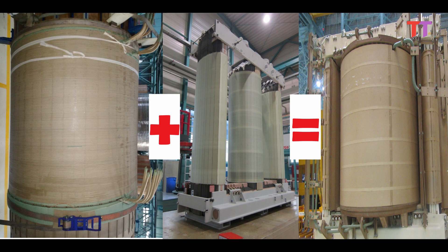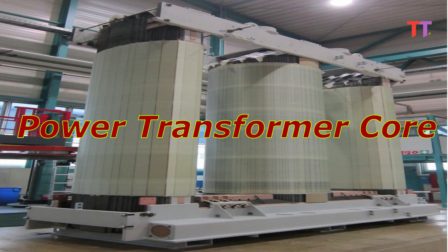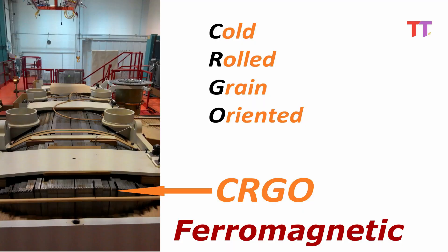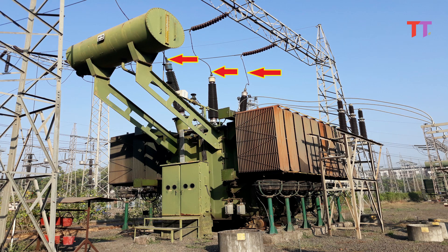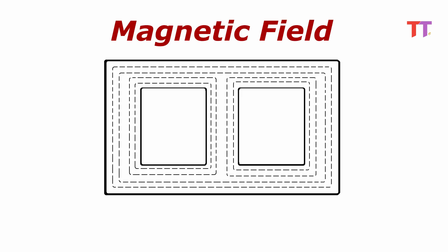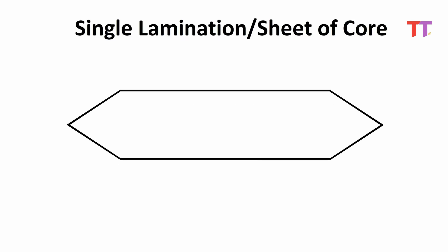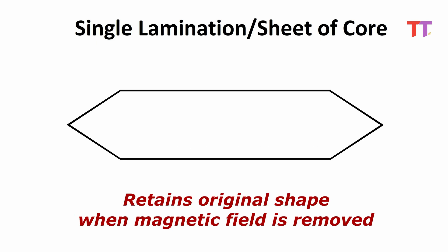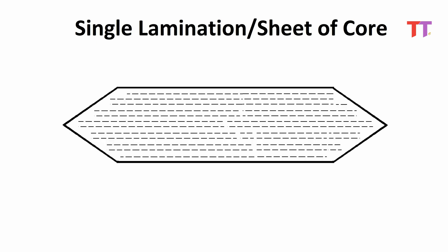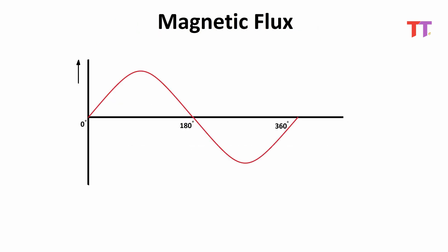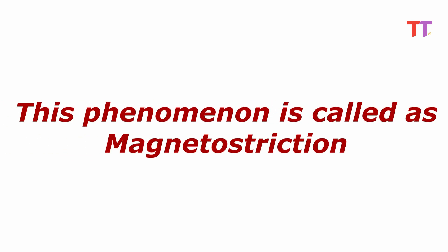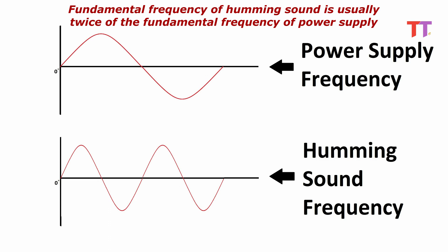As we have seen in one of the previous videos on manufacturing a power transformer, the transformer core is made of CRGO, called Cold Rolled Grain Oriented, which is ferromagnetic. When the transformer is charged — that is, when AC power is given — a magnetic field is produced which causes the core to change its shape. The core extends itself when exposed to a magnetic field and retains its original shape when the magnetic field is removed. Hence, the core continuously extends and retains its shape with flux variation. These shape variations cause vibrations and consequently the humming sound. This phenomenon is called magnetostriction.